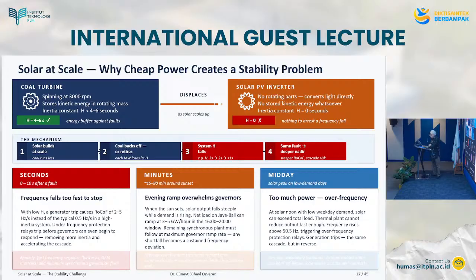And midday, solar peak on low demand days. That means you're going to have too much power with a solar dominated system. Too much power means over frequency. At solar noon, with low weekday demand, solar can exceed total load. Thermal plant cannot reduce its output fast. So they've got to ramp up and ramp down, right? It's not like a light switch, put on, put off, right? So it's got to increase and it's got to decrease, and they've got a rate. It's like a car, acceleration and deceleration. It cannot be done instantly.